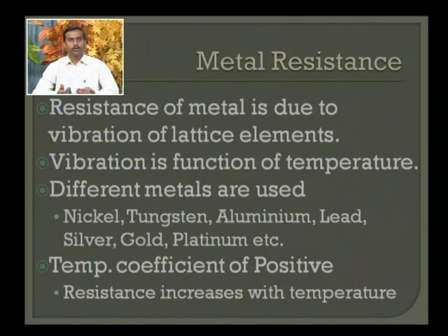Depending on the sensitivity that you require, you need to go for different materials or different metals of manufacturing. For example, PT100 has a 36 ohm increment at 100 degrees Celsius, meaning its sensitivity is somewhere around 0.36 ohms per degree Celsius. So this is the sensitivity of platinum. If I go from platinum to gold or silver, the sensitivity is smaller, but if I go with a higher resistive material, then the sensitivity will be comparatively higher.